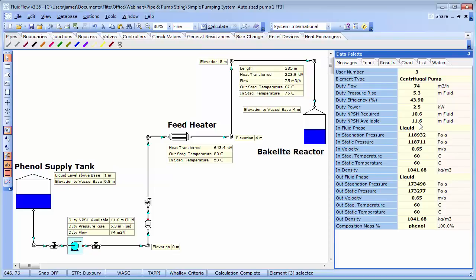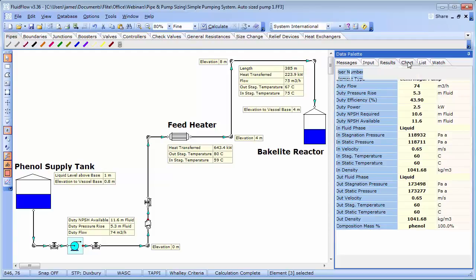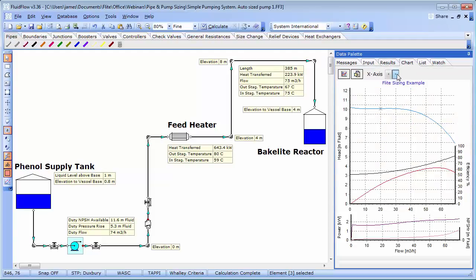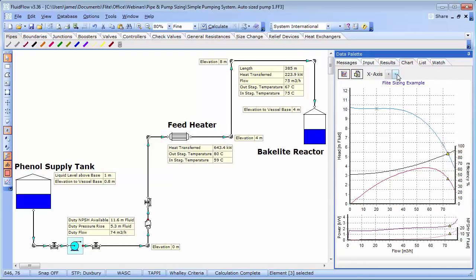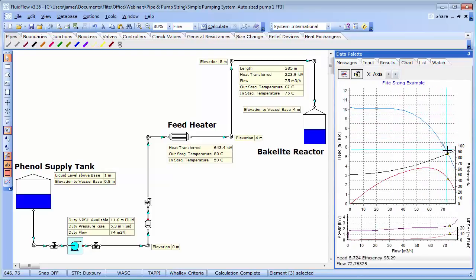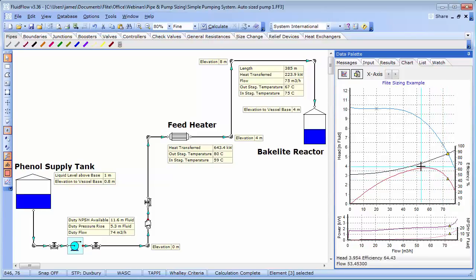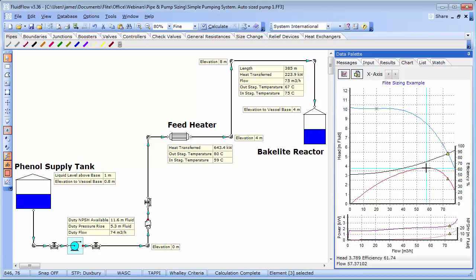This particular operating condition develops a ratio of 1.09, which is just below this recommendation, so perhaps not an ideal solution. A quick check on the pump curve illustrates just how the pump performance has dropped off. We can see the efficiency is 43%. Let's have a look at the curves. And we can see we've dropped off the optimum position of the capacity curve, and we're quite some distance now from the best efficiency point on the rate efficiency curve. Let's return our pipes to the economic solution of 150 millimeters.